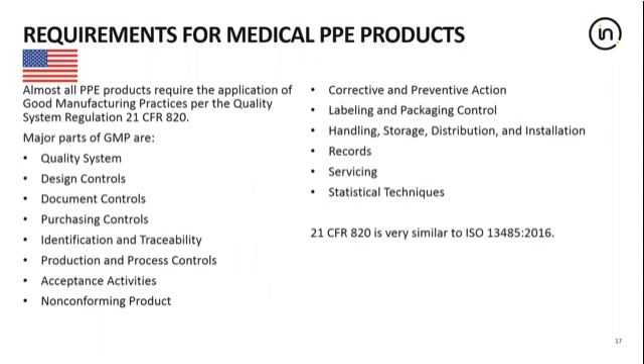Most products which are covered under this legislation require that the manufacturing processes meet that regulation of 21 CFR 820. This regulation is very similar to the international standard ISO 13485, which is the certification standard for medical devices quality systems, and it is expected that eventually the FDA will harmonise the regulation with this standard. The sections of the standard and the regulation are typical of quality management system in that the requirements are set for production control, design control, and verification, and procedures should be set out to identify any non-conforming products.